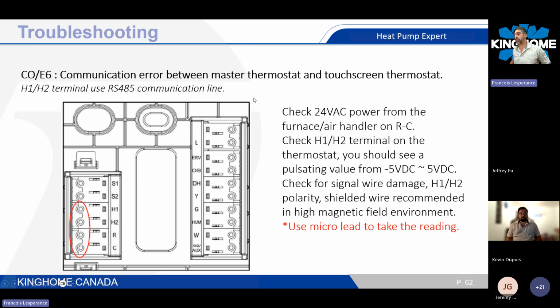So getting back to troubleshooting, guys. H1, H2 is an RS485 communication line. This is not really something you can easily measure with your multimeter, but there's still a way to find out if there's a problem with that thermostat. The white thermostat, the one in the mechanical room, is the sender. On H1, H2, right here, you will have a pulsating value from -5 to +5 volts DC. So it will always be fluctuating.